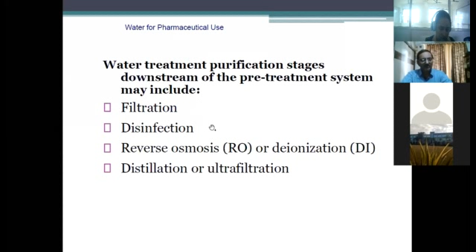This is a typical deionizer design where you have two columns. One is a cationic column, one is an anionic column, and any raw water comes from the water softener. So the water is coming from the water softener. It passes through one column, then goes into the other column. So anions and cations will be adsorbed on the ion exchange columns. Then it goes to a cartridge filter of 5 micron, another cartridge filter of 1 micron. It is ozonized, so there's an ozone generator. Then it is heated to the required temperature, and it goes again for recycle. So this is the recycle loop.